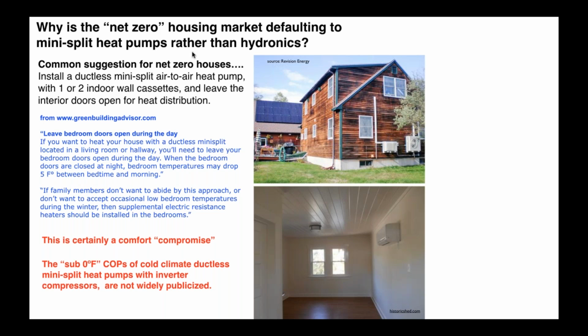So one of the things you'll see with this kind of heat pump, several manufacturers will talk about the fact they can maintain capacity at sub-zero Fahrenheit temperatures. Ask them about COPs at -10 or -15 or -20 degrees Fahrenheit. Those COPs are not good, okay?